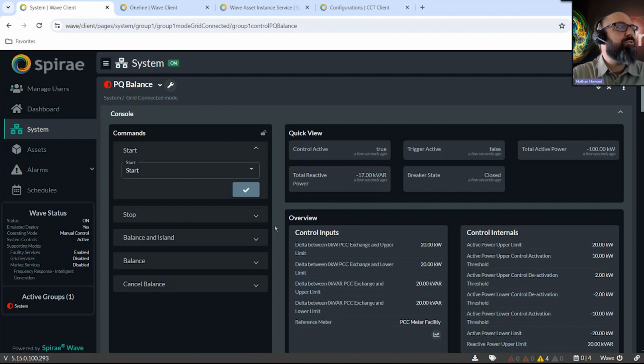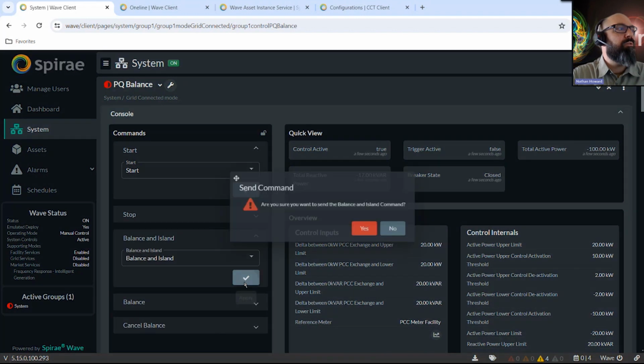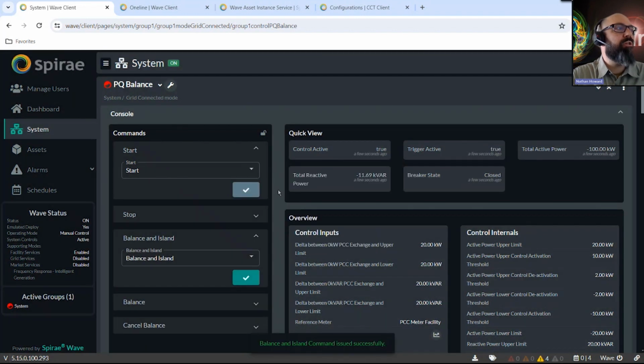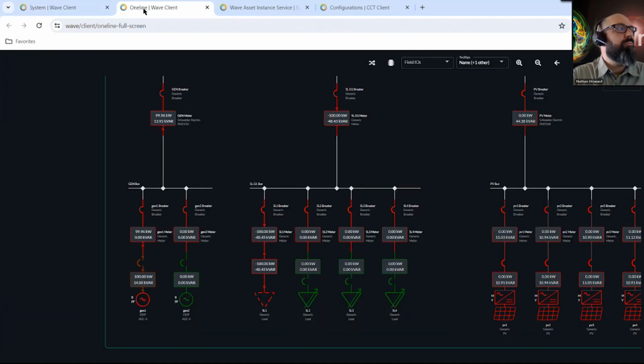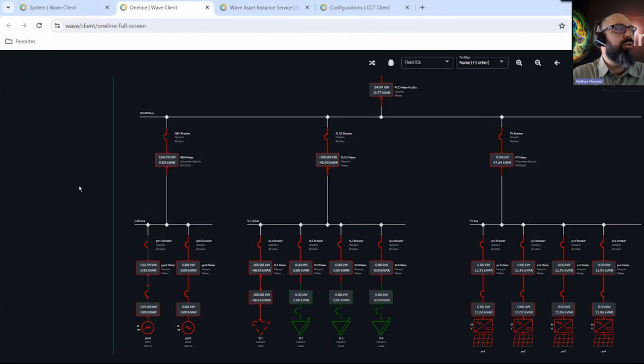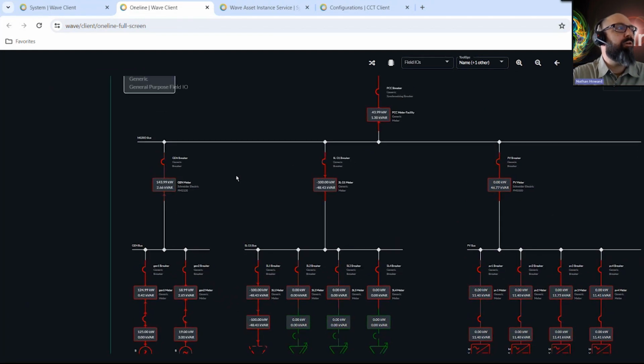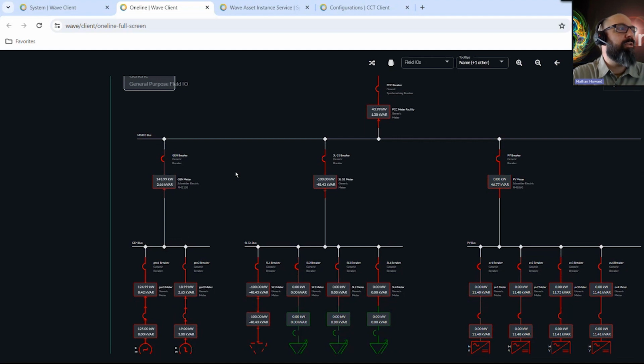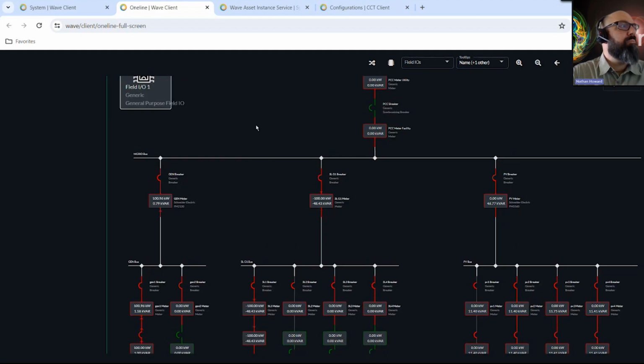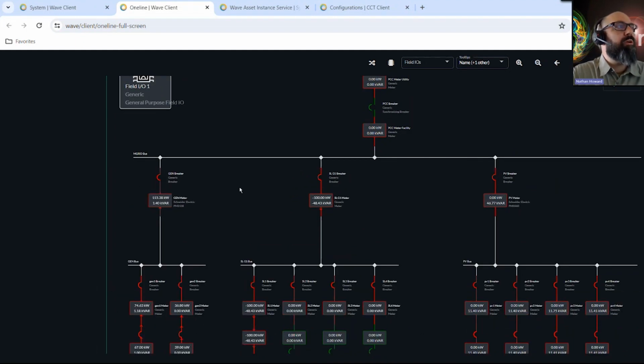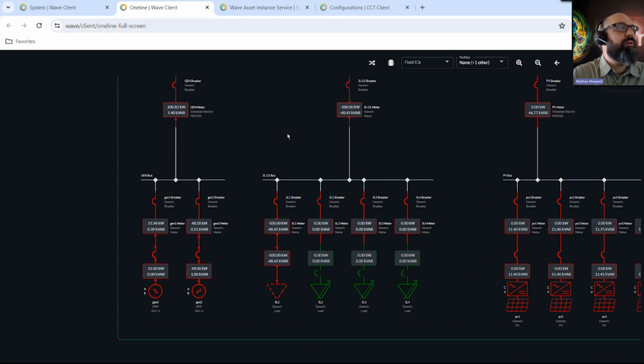And so when we start that PQ balance, that's going to look at the active and reactive power flow across the PCC. So we'll go ahead and initiate that action now. And we'll start ramping up that conventional generation to meet the load of the system, reducing our consumption from the grid. And once that consumption from the grid is 0, then we'll open that grid breaker up and we'll be operating in an island state. So there you go. You can see, brought up the generators, open the breakers. So now we're operating in an island mode.